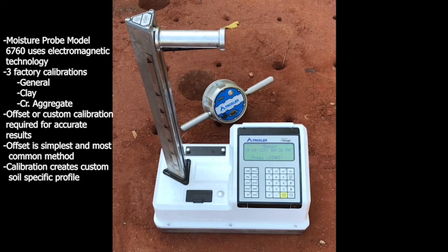The benefit to the moisture probe calibration option is that it forms an actual calibration which will address the adjustment of the moisture readings at various moisture levels. If the soil has a wide range of moisture contents, this is a better option. The moisture offset adjusts the reading at the moisture level which the offset was determined for. This is often acceptable because it is common and desirable for the moisture content of a soil to be near optimum.